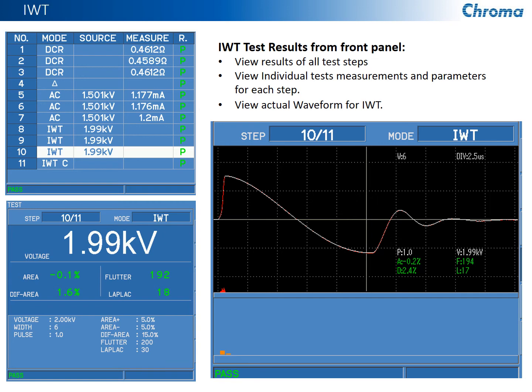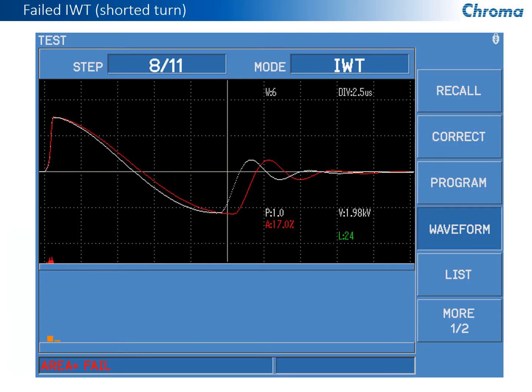Down here you'll see it gives you area, differential area, flutter, and the Laplace test results, and will be used for judgment. If it comes up all green, you know you're good. Any one of those come up in a red, you know that it's failed. I'll show you an example here of a failed unit. This fails by area. The area test that we did for this one, the actual judgment was done at, I believe, 15%. You can see here that it failed by going up to 17%.